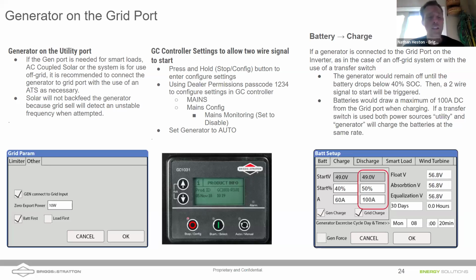Yep, thank you, Nathan. Maybe address that zero export power there. So the zero export power that is there on the screen: whenever you have two sources of power, like solar coming in and/or generator coming in, there is the potential to send a little bit of power back the other direction, right? And it has to do with the phase of the power that's coming out. So that's the amount of tolerance, to my understanding. I was asking Sol-Ark this yesterday. That's the amount of tolerance that you're willing to accept to have power go the reverse direction. So 10 watts is not going to burn out your generator if you have solar powering your loads and adding a little bit to the AC bus. I don't know it better than that. Certainly you can reach out to Sol-Ark, but that's what they've let me know the tolerance is.